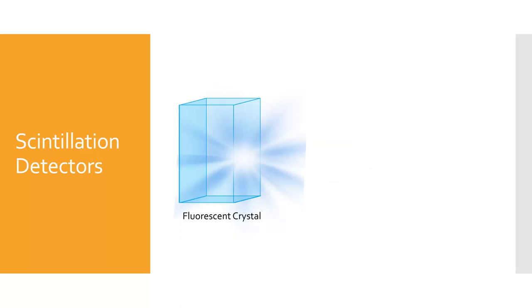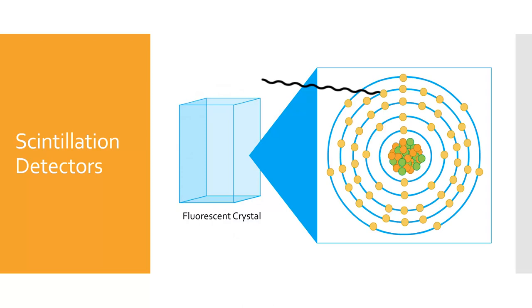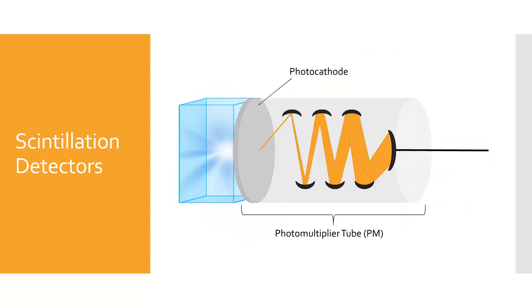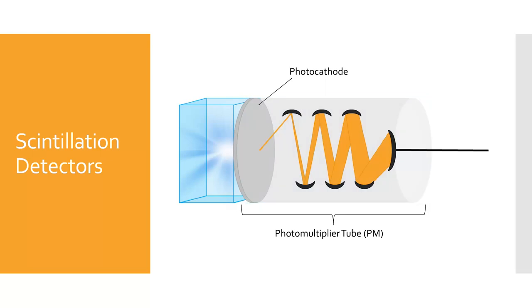Next, we will look at scintillation detectors. Scintillation is the immediate emission of light when struck by radiation, sometimes referred to as fluorescence, and it takes place in a special crystal. When the radiation interacts with the crystal, an electron in the crystal's atom is moved to a higher electron shell, but it doesn't stay there. The electron immediately falls back into place, giving off energy as visible light. That burst of light is converted into electrons when it strikes the photocathode of the photomultiplier tube, or PM tube, through the photoelectric effect.